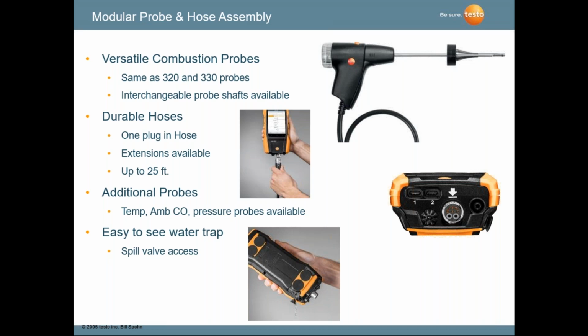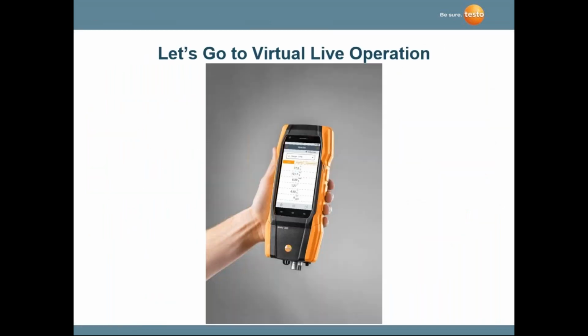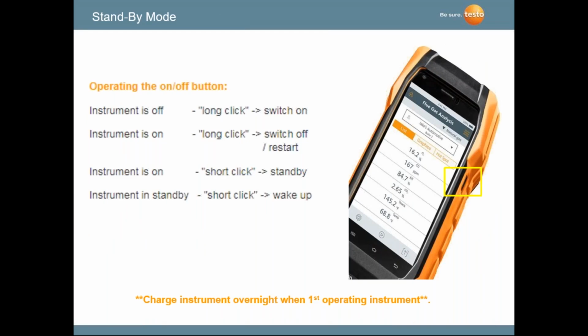Obviously, when we're bringing in flue gases, they're hot, they're wet, they're dirty. So we have a particulate trap at the back of the probe handle, and the water trap is at the base of the instrument, where you've got to keep your eye on. There are water levels, and if you exceed a water level, you want to be able to dump out the water from the analyzer itself. The on-off button is very quick. The warm-up time on a combustion analyzer with Testo is a 30-second warm-up. We also added a feature where you can go into a standby mode. So if you're in the same boiler room and you need to do 2 or 3 boilers, you don't have to keep shutting the instrument off and turning it on. You can just go into a standby mode.